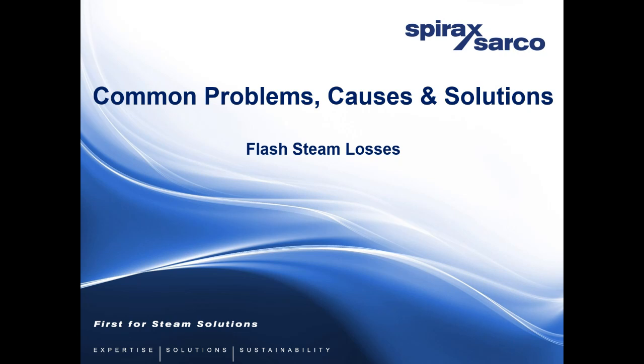So we would expect to see your feed tank, an open to atmosphere feed tank, at around 85 degrees, because that is an indication of how much water you're recovering, but also it protects against the inefficient use of your fuel for your steam boiler. The hotter the condensate you can return, the less thermal shock you give to your boiler, the shorter the re-steam times are to your boiler. So there's many reasons to return as much condensate as possible. One of which is water recovery, so that you use less water, but it's also energy.